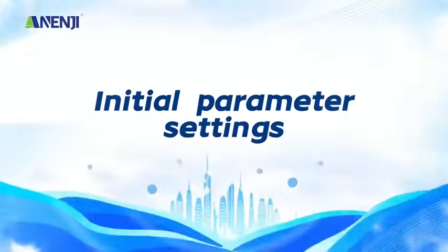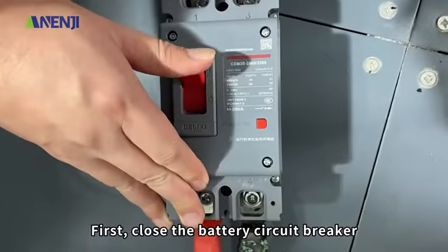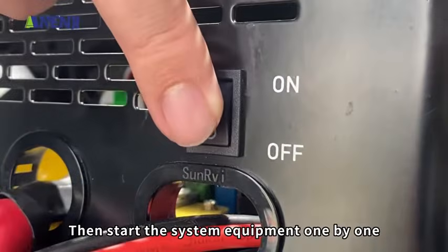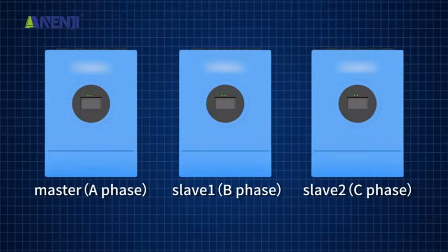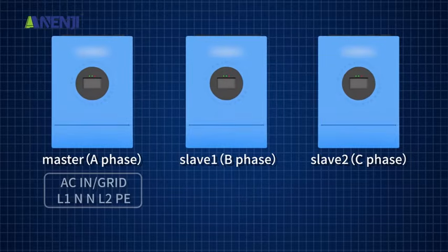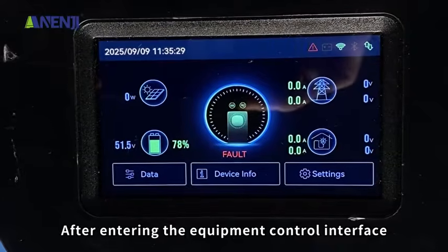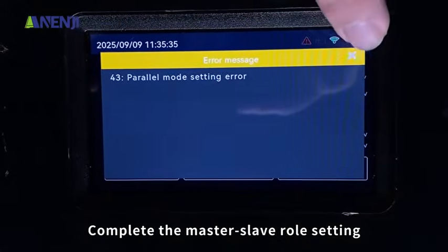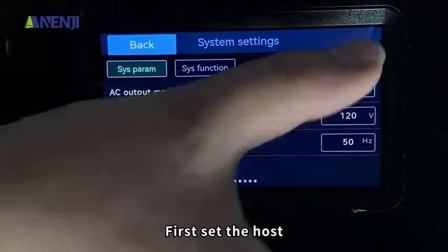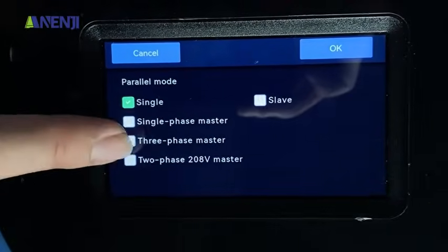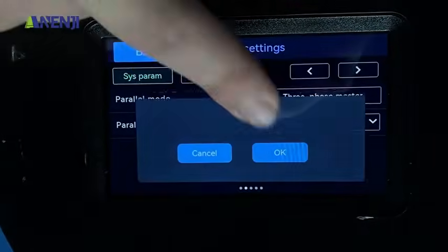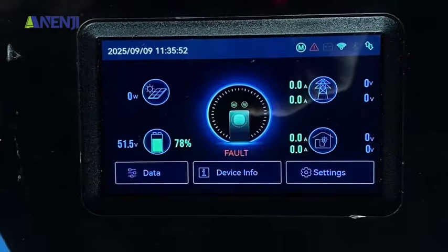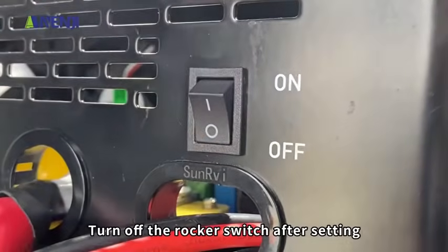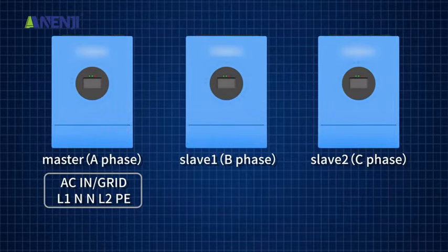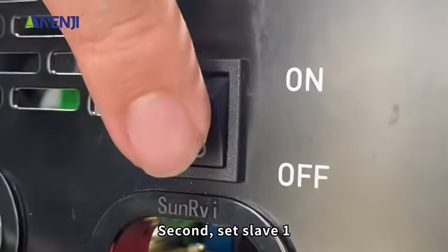Initial parameter settings. First, close the battery circuit breaker. Then start the system equipment one by one through the rocker switch. After entering the equipment control interface, complete the master-slave role setting and phase parameter configuration. First, set the host. Turn off the rocker switch after setting. Second, set slave 1.